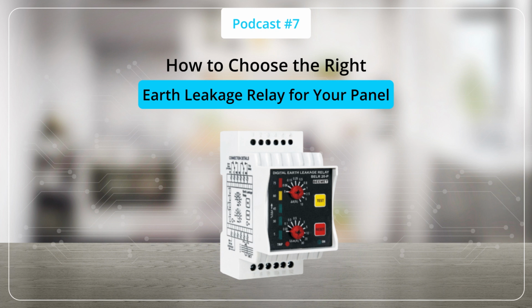The earth conductor should never pass through the CBCT, as this can interfere with proper leakage detection. Another critical part of the installation is the trip circuit. The ELR output contacts are connected to the shunt trip coil or undervoltage release coil of the molded case circuit breaker, commonly known as an MCCB.